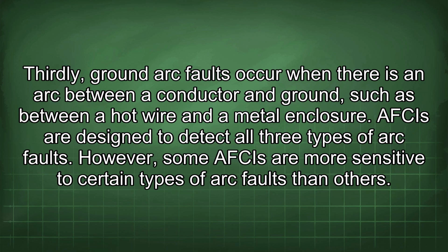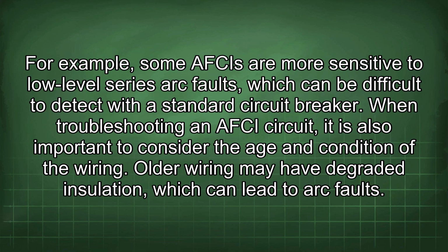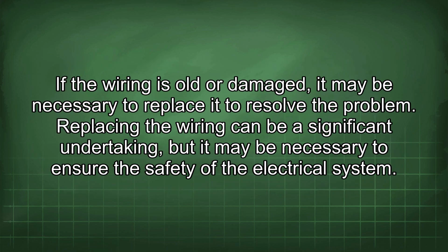However, some AFCIs are more sensitive to certain types of arc faults than others. For example, some AFCIs are more sensitive to low-level series arc faults, which can be difficult to detect with a standard circuit breaker. When troubleshooting an AFCI circuit, it is also important to consider the age and condition of the wiring. Older wiring may have degraded insulation, which can lead to arc faults. If the wiring is old or damaged, it may be necessary to replace it to resolve the problem.